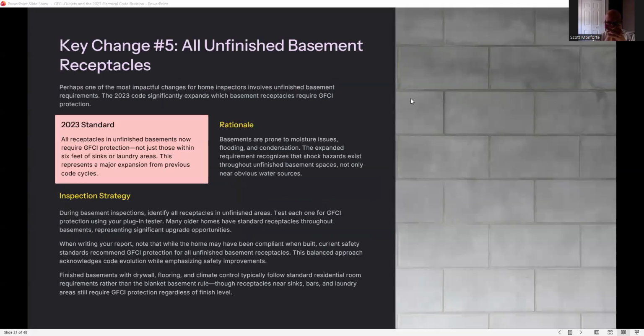Key change 5, all unfinished basement receptacles. Perhaps one of the most impactful changes for home inspectors involves unfinished basement requirements. The 2023 code significantly expands which basement receptacles require GFCI protection. Under this 2023 standard, again, all unfinished basements now require that protection, not just those within 6 feet of sinks or laundry areas. The rationale: basements are prone to moisture issues, flooding, and condensation. The expanded requirement recognizes that shock hazards exist throughout the unfinished basement spaces, not only near obvious water sources.